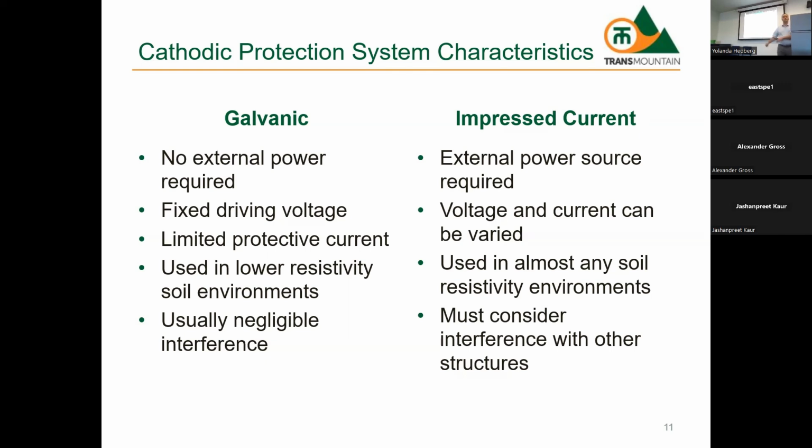In an impressed current system, we use an external power source, so now we can alter how much voltage we're using or how much we need. Okay, that's the main difference between the two. And impressed current systems can obviously protect much further away, bigger systems.